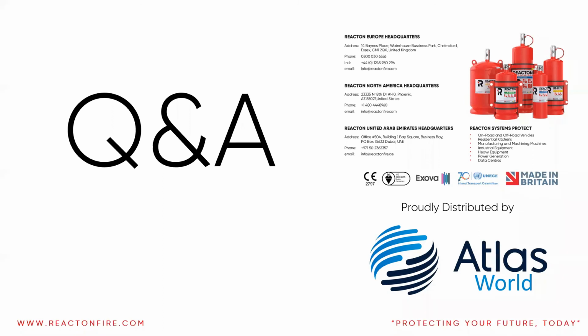Yeah, like you said, the cylinders have a 10-year shelf life according to the PED regulations. But the agents themselves, for example, the 3M Novec 1230 and the FM200, pretty much have an indefinite lifetime as long as they're stored correctly. So it's really the cylinders that are driving the 10-year change.